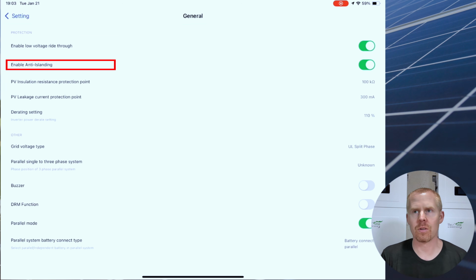Anti-islanding is when you have a grid connection and you are either selling back to the grid, or I believe it also works with the normal load aspect. So when anti-islanding is enabled and your grid goes down, then the inverter will stop trying to push power through that AC input and send it back to either your main panel or to the grid. It's a big safety feature to prevent power from going on the grid lines should the grid go down.